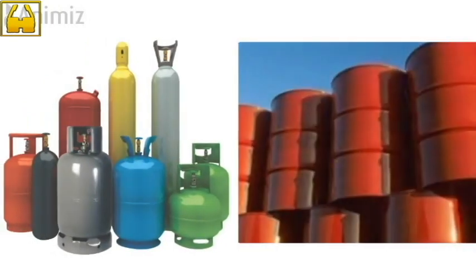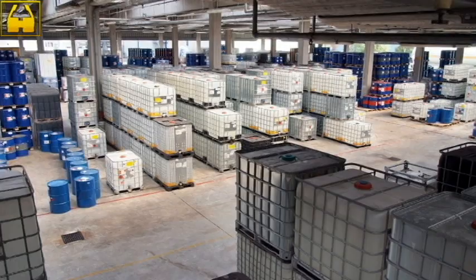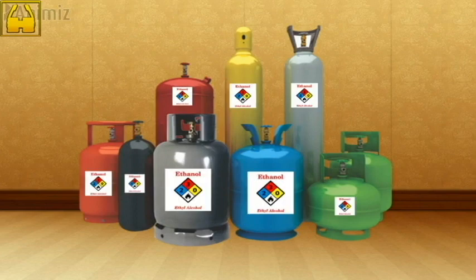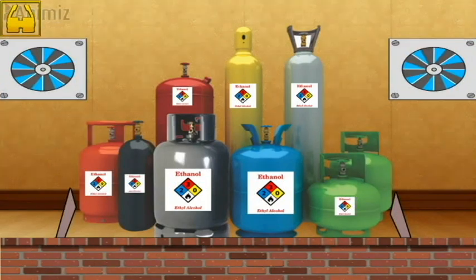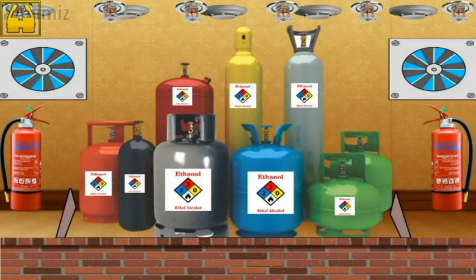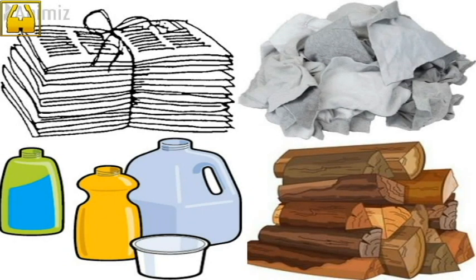Controlling source of fuel: all combustible and flammable materials must be removed or limited. Chemical storage should have the following precautions: separate storage area, compartmentation, labeling for chemicals, spill trays, bund wall, and proper ventilation. Firefighting equipment such as fire extinguishers, smoke detectors, fire hoses and water sprinklers, along with safety signages and barricading, should also be provided. Solid combustible materials such as wood, paper, cotton and plastic must be disposed from the site or covered by a fire blanket.